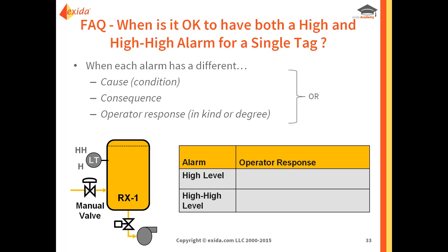Let's look at an example where both alarms are justified. For a tank where the operator controls a manual valve, the response to a high-level alarm would be to partially close the valve to reduce flow. But if that doesn't work and the level continues rising to the high-high level, the operator would close the valve completely to stop flow entirely. This shows the response is different in kind or degree between the two alarms — one case is reducing flow, the other is fully shutting it off.